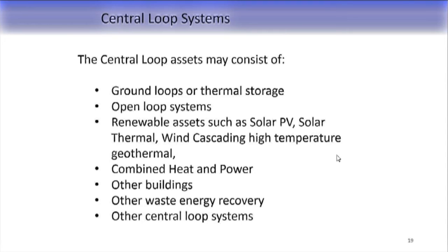Wendy's, back during that time, found out they could put in a CHP unit, a little generator, and heat recovery. About 10 o'clock, when rates in Southern California started to come up, they'd crank on the generator, pull the breaker on the main power system, make all the hot water needed to keep the restaurant clean, and all the energy needed until 2 or 3 o'clock when the peaking goes away, then the generator turns off and they go back on city power.